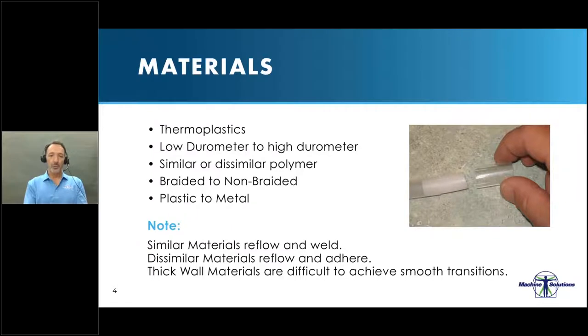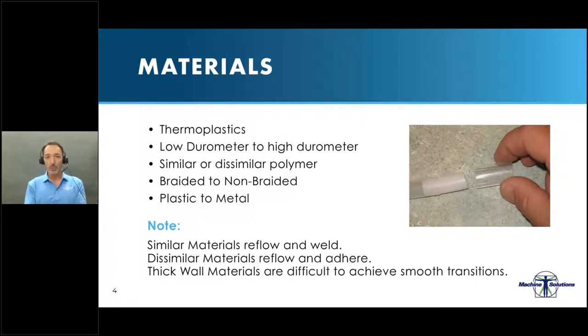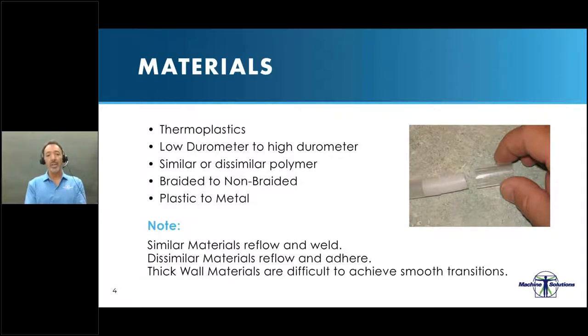The reason you would choose a lap joint is because you have dissimilar materials, where one material is going to adhere to the other. At least one of the materials must be a thermoplastic. That means you can have high durometer to low durometer materials, braided to non-braided, similar to dissimilar polymers, and even plastic to metal. In the case of identical materials, those materials will create a weld and become one polymer again. In the case of dissimilar materials, one material adheres to the other.